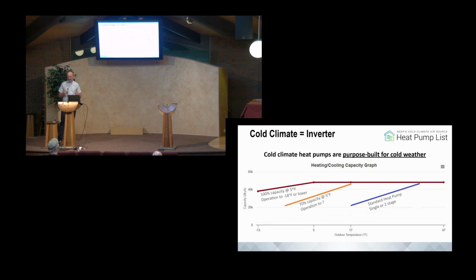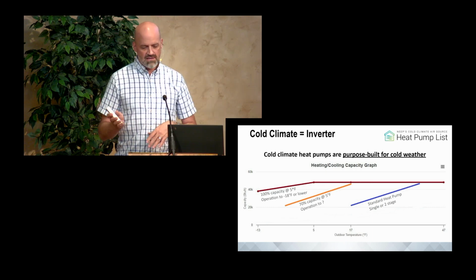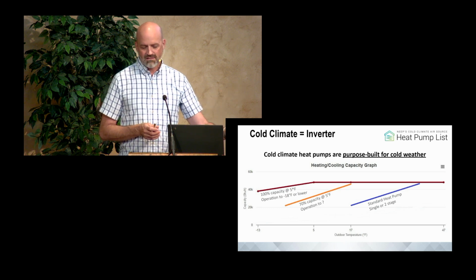There's different capabilities of what people are calling cold climate heat pumps. The blue line there is really a standard heat pump, the one people refer to when they say they don't work in our cold climates—they're thinking of older technologies like that. That blue line shows the dropping off of capability as temperature drops, shown along the bottom from 47 degrees on the right to negative 13 on the left.